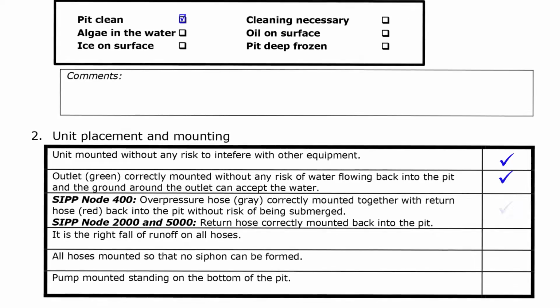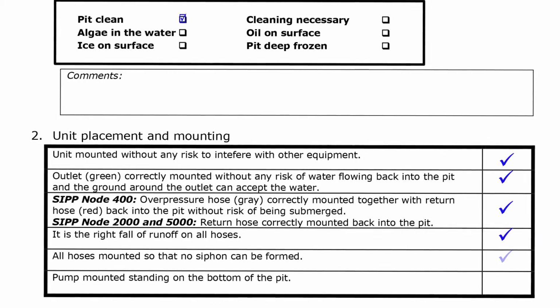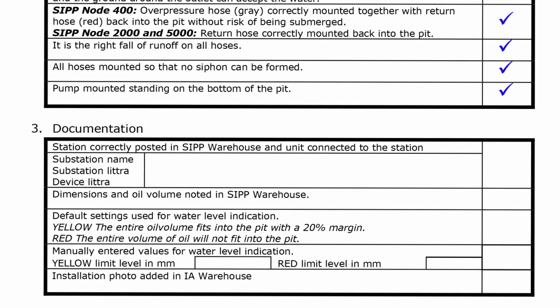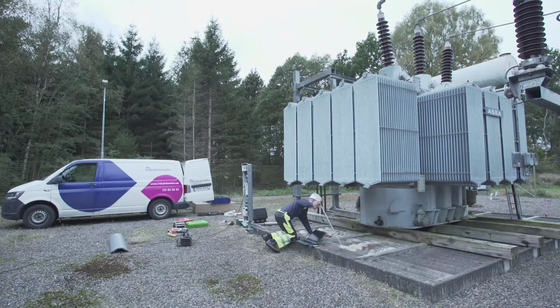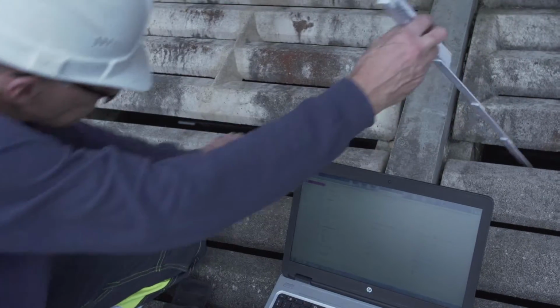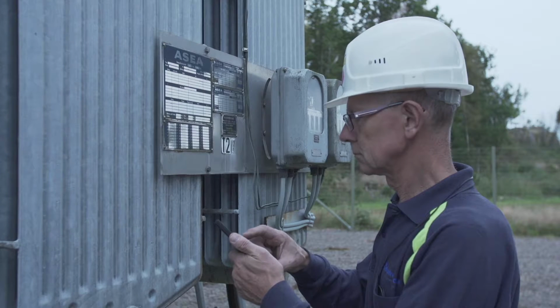Check the placement and installation of the unit. Configure and do the documentation in the IA warehouse. Enter substation name, litera and device litera. Measure the dimensions of the pit, the transformer oil volume, and enter the numbers in IA warehouse.